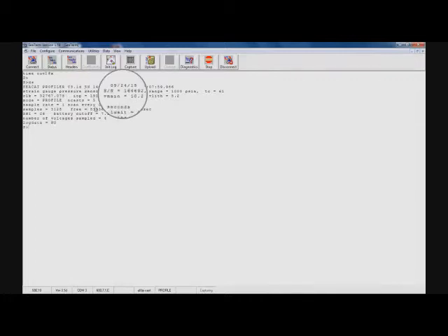Here we can see a number of things. We can see the voltage on the main batteries. These are the D-cell batteries in the CTD, and at the moment we have 10.2, which is fine. If we're getting down towards 9 volts, then you should probably look at changing these. We can also see the mode that the CTD is in, and currently this is in profiling mode.